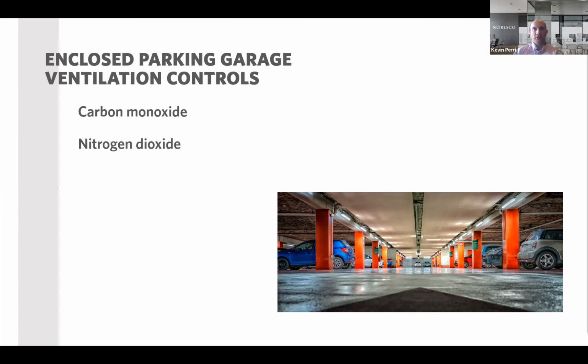Now there are some exceptions, as with every rule in the code. The exception is if the total exhaust capacity is less than 8,000 CFM, then you're exempt. The old code had a much larger number for that exemption, roughly 22,000 or 23,000 CFM. So if your exhaust was less than 22,500 CFM, you didn't need to have this interlock with your exhaust fans. Now what they said is if it's 8,000 or less, you don't. So anything above 8,000 CFM needs to be interlocked.